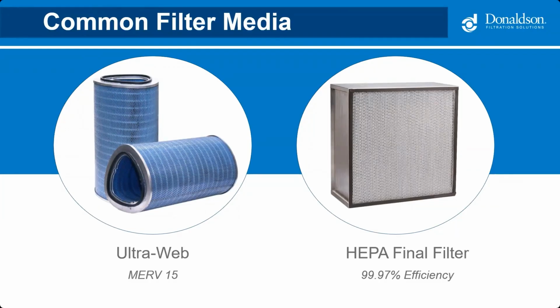It's 99.97% efficient, but it's not uncommon to also see our ULPA or ultra low particulate air filters that have a greater efficiency of 99.999%. But if you have VOCs in your airstream, I think I saw a question about this earlier, you should consider a carbon after filter instead of HEPA. HEPA will not be able to filter out VOCs, but a carbon after filter can.